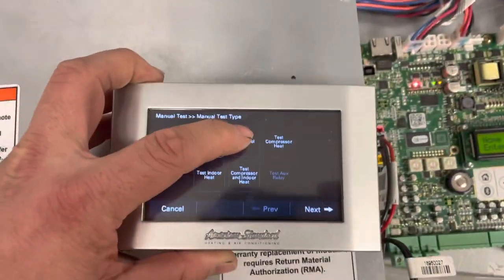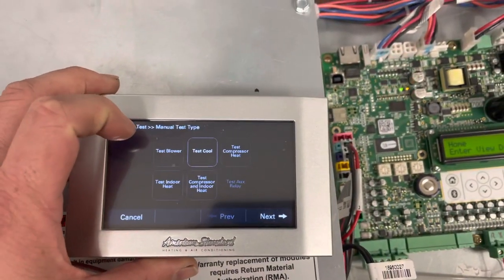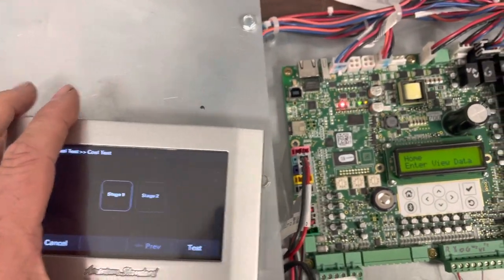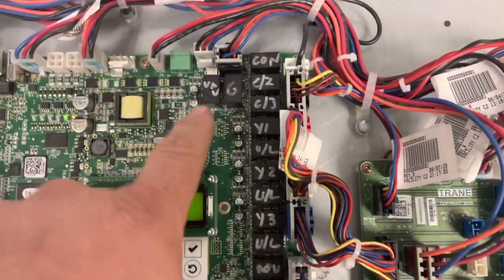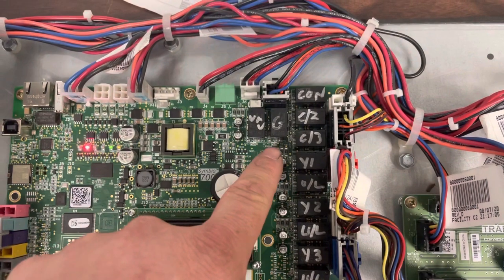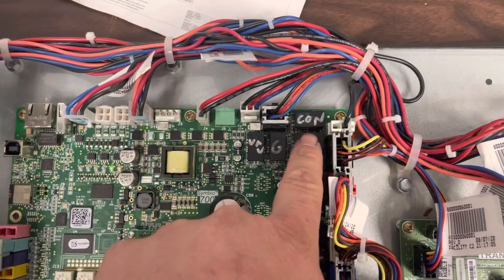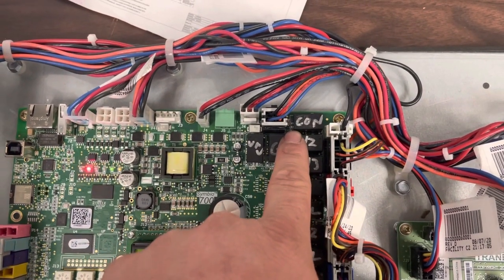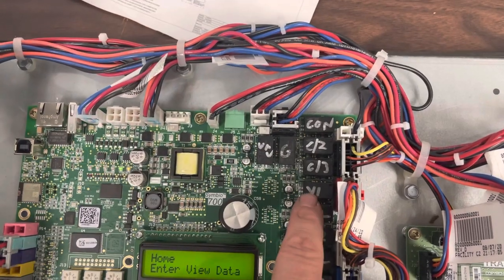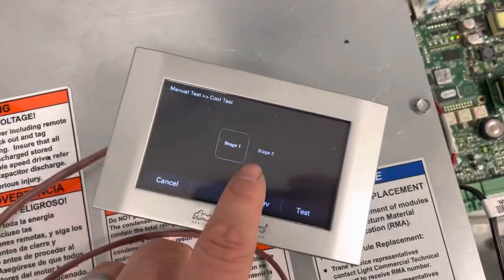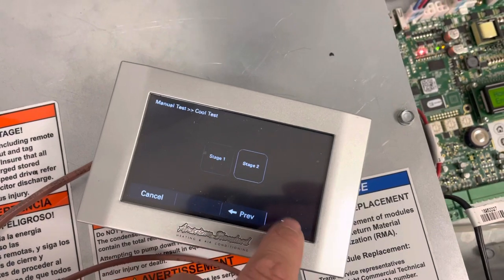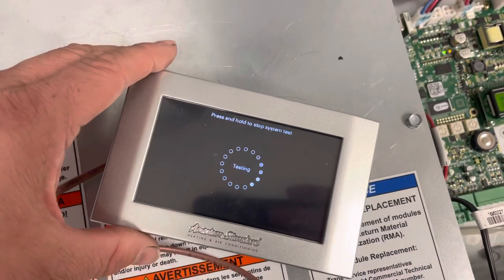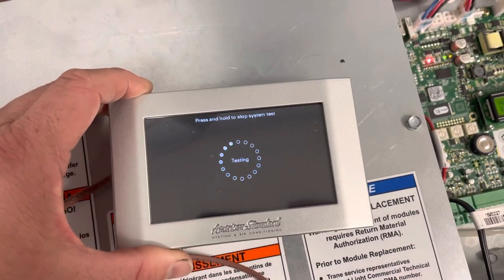I'm going to go to test cool next, and then remember I've got these labeled. So that's G, that's going to be my call for the blower. CON is going to be condenser fans, you have a green LED there. And then I'll get my Y1, my Y2 to light up. So I'm going to go to stage two test and we're running that.